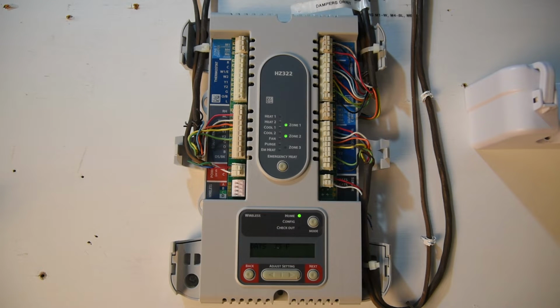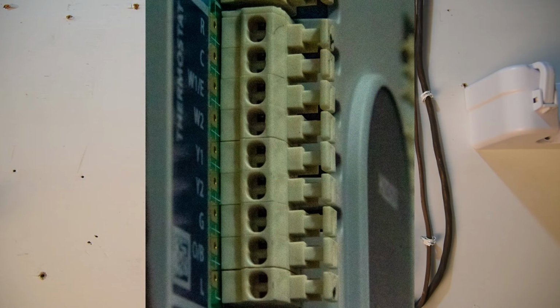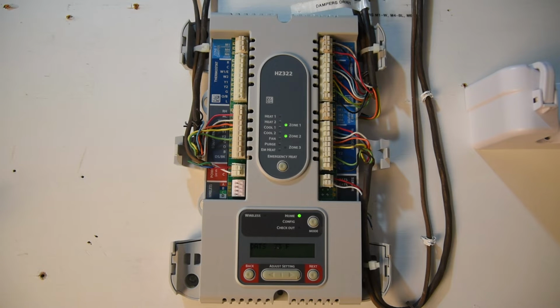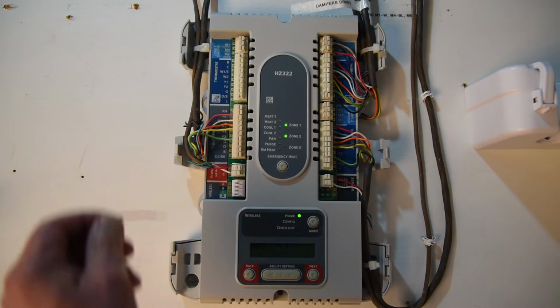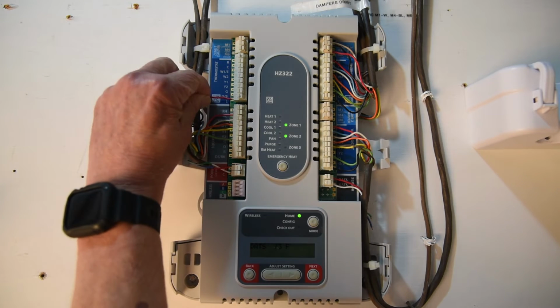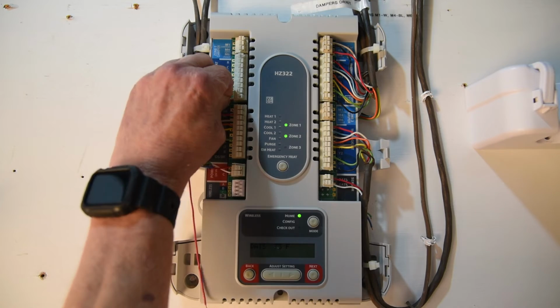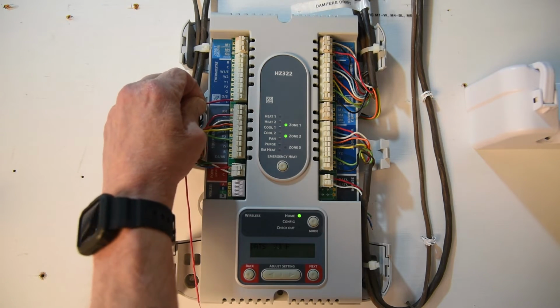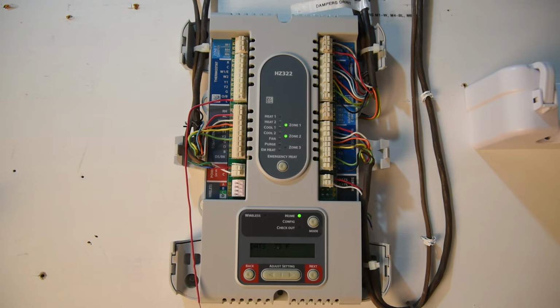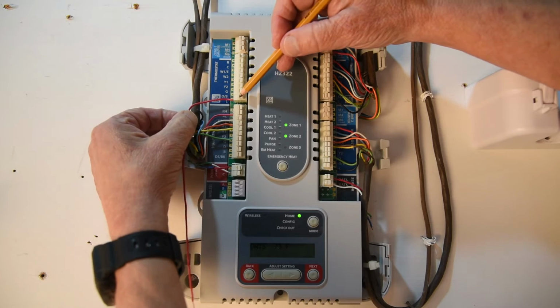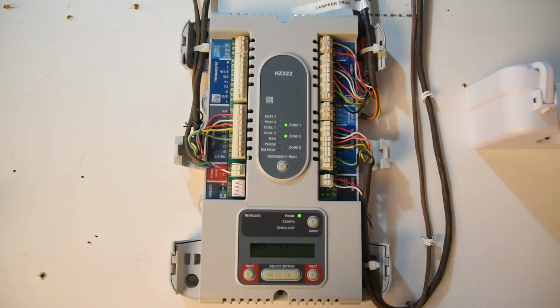To wire this, you look at this picture, you'll see that each of these little ovals on the side has 2 holes in it. That is where you're going to have to get the wire in. Not just the oval, but there's a hole at the top and bottom of the oval, and your wire has to go into one of those holes. Here you will push it in, and it secures in there. If you need to take it out, you push this in and then pull it out. All of those terminals work that way.